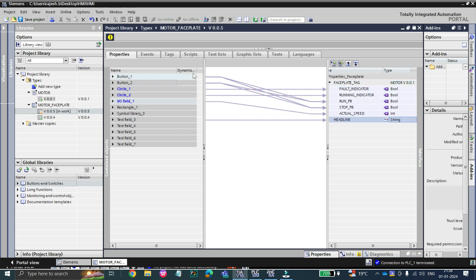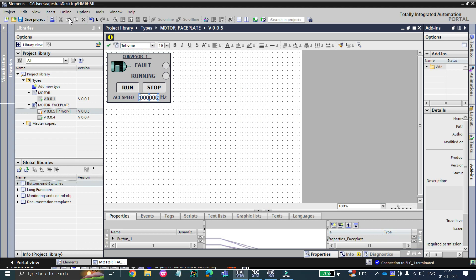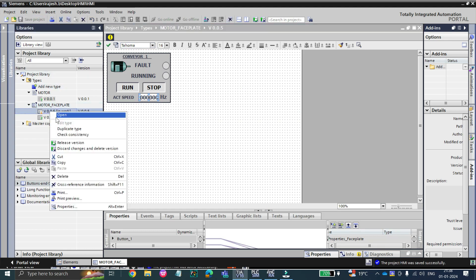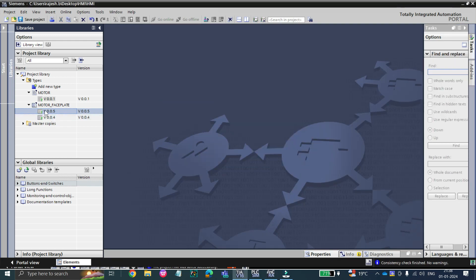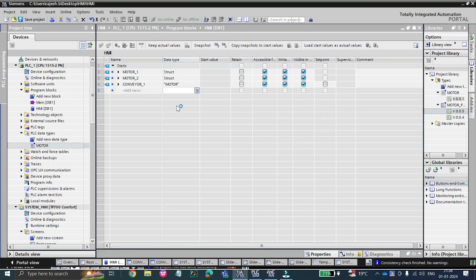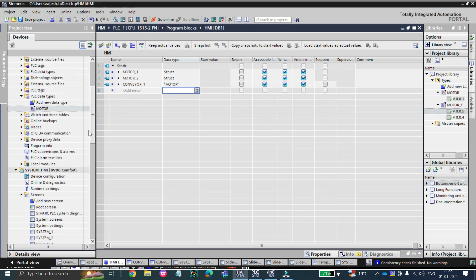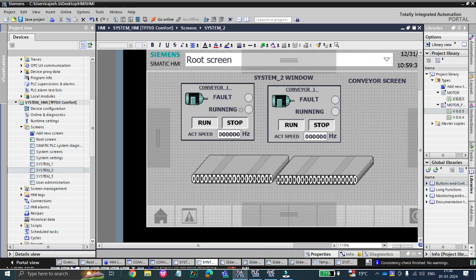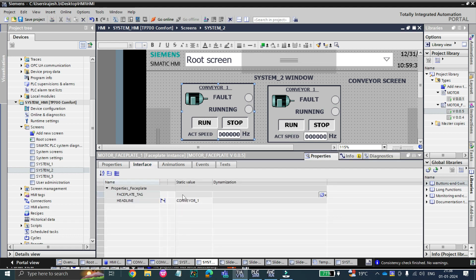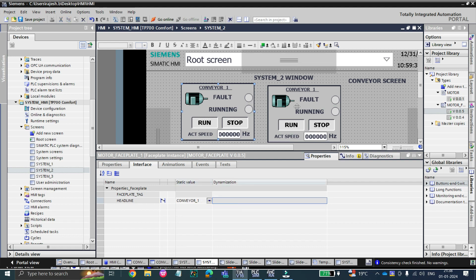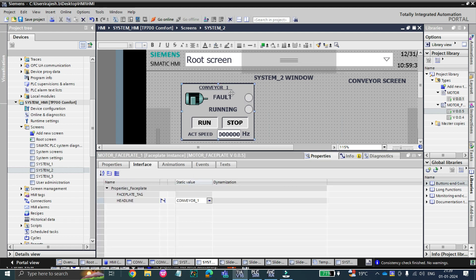Now we are done with our faceplate. Let's release the version — don't delete the older version; update it to the most recent version, and version 0.0.5 will be released. Press start, and you can see conveyor 1 motor is there. On this screen, you can see that earlier there were many types of interfaces, but now we only have one interface called 'faceplate tag' and one for the headline tag.